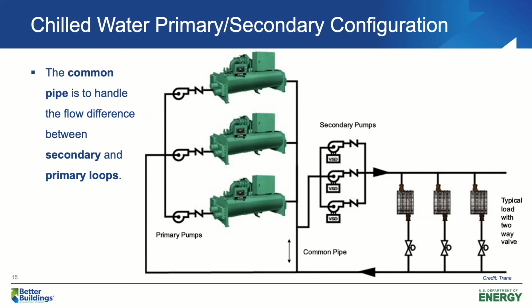So in other words, the secondary pumps will overcome the pressure loss across the pipelines, across the cooling coils, and make sure that we will get chilled water to those cooling coils. But for primary pumps, their job is very simple: only overcome the pressure loss across the evaporators of chillers. Here you can see that we have a small common pipe between the primary water loop and the secondary water loop. When the chilled water flow rate in the secondary loop is less than the primary loop, the excess chilled water flow will go through the common pipe and go back to primary pumps to make sure that our chillers will have the same amount of water flow all the time.